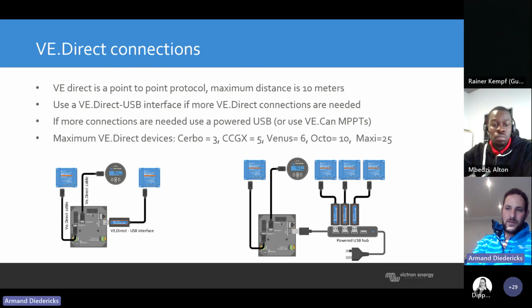So as you see, the VE.Direct cable goes to the V, there's two VE.Direct ports on the GX device, CCGX device. If you need more, you've got the hub. A BMV - if you've got old batteries or a bad lithium battery, install a BMV with a shunt to get the accurate reading, and that also communicates via VE.Direct cable. Then you've got your MPPT, also VE.Direct to USB. Your energy meter goes from USB to RS485, but that's also USB interface.